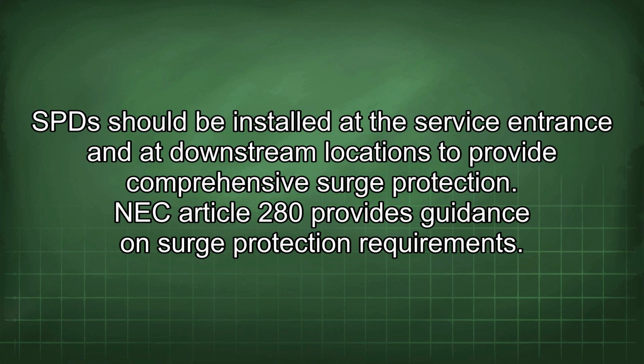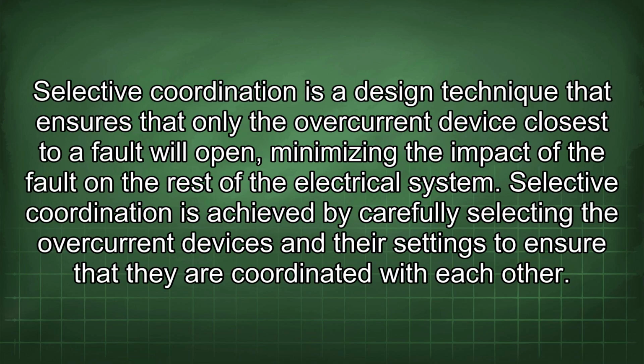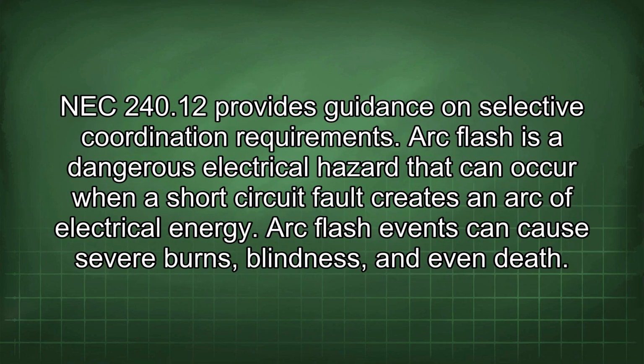NEC Article 280 provides guidance on surge protection requirements. Selective coordination is a design technique that ensures that only the overcurrent device closest to a fault will open, minimizing the impact of the fault on the rest of the electrical system. Selective coordination is achieved by carefully selecting the overcurrent devices and their settings to ensure that they are coordinated with each other. NEC 240.12 provides guidance on selective coordination requirements.